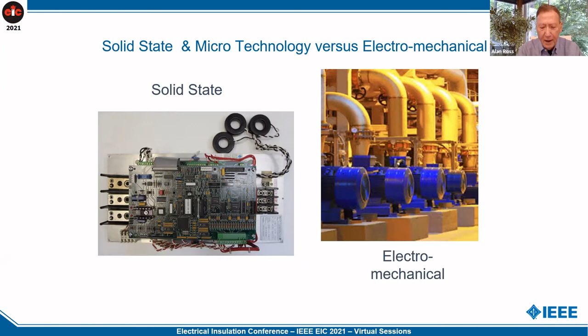In this world where we're changing out using microtechnology, even nanotechnology, it does have an impact on the electromechanical system, because the electromechanical system is forgiving. In solid state technology, it's not as forgiving. So we better be more careful about what we specify in terms of insulation.